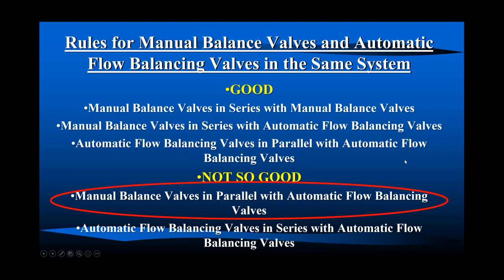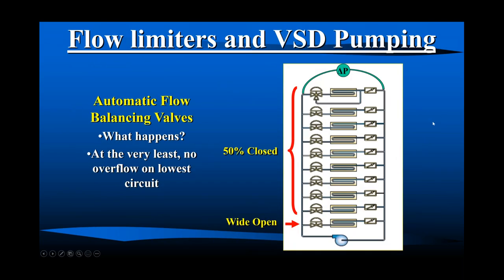So let's talk about that. Where do we see this occur? Manual balance valves in parallel with automatic flow balancing valves. Let's go back to our flow limiters and variable speed pumping. Automatic flow balancing valves, here they are. And we said that if this was wide open and these were modulating closed, at least we wouldn't overpump this bottom terminal unit. That's usually okay, but sometimes it's not okay.